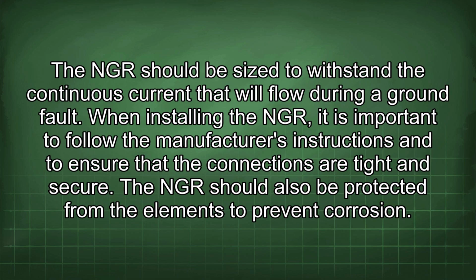The NGR should be sized to withstand the continuous current that will flow during a ground fault. When installing the NGR, it is important to follow the manufacturer's instructions and to ensure that the connections are tight and secure. The NGR should also be protected from the elements to prevent corrosion.